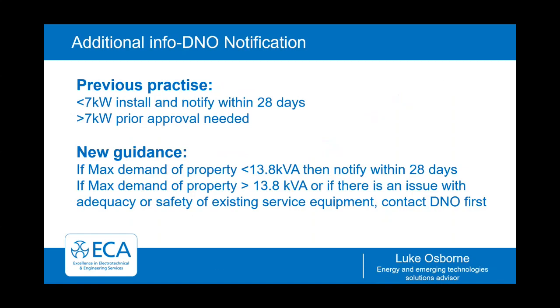Additional information, previous DNO notification. All DNOs have their own specification essentially, so it's worth checking with DNOs. But the previous practice was if the installation of the electric vehicle charge point was less than 7 kilowatts, you could install and notify the DNO within 28 days. And if it was above that, prior approval was needed.